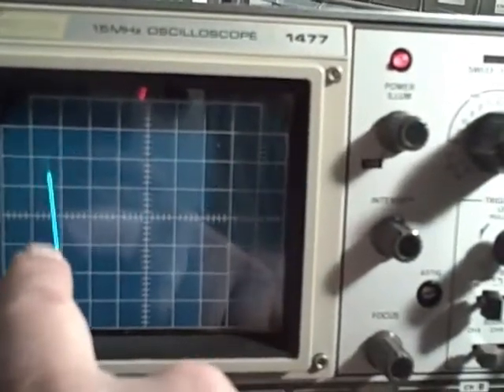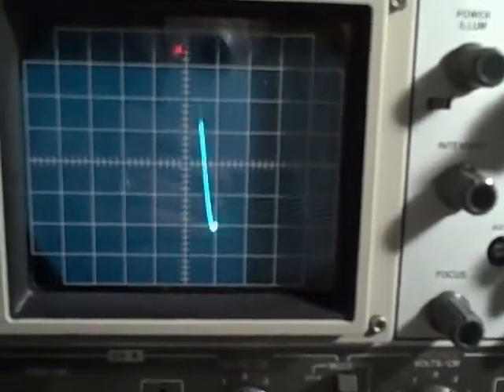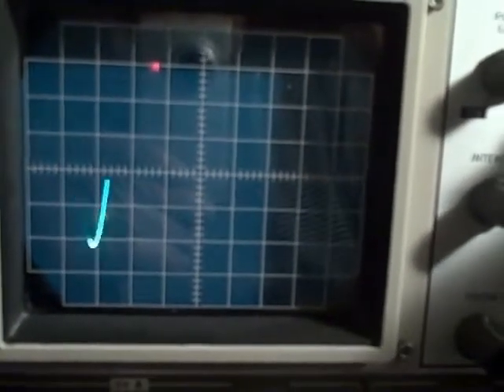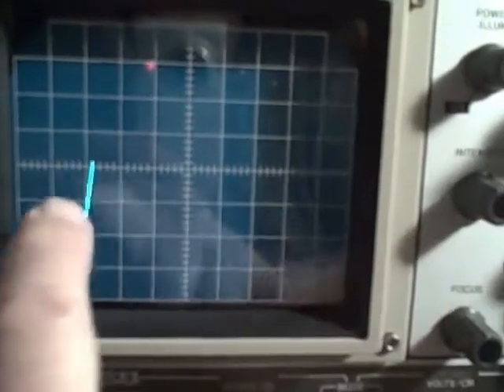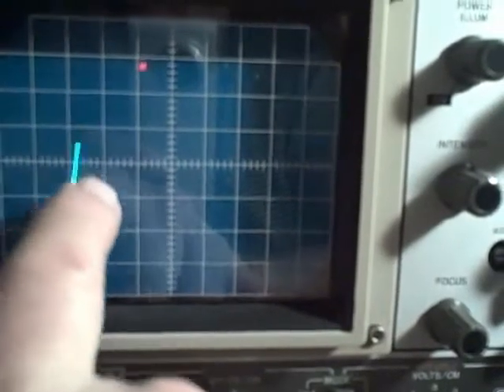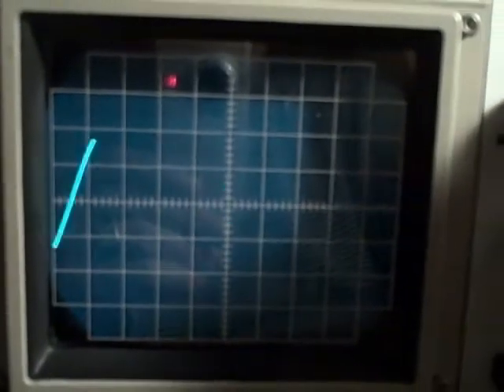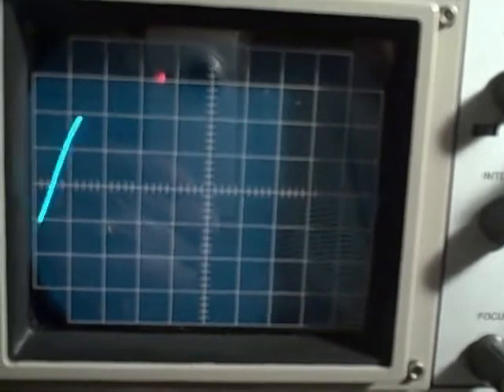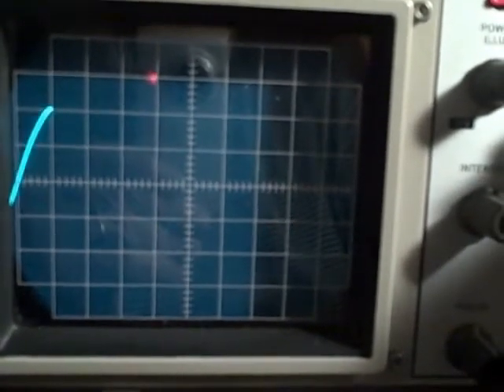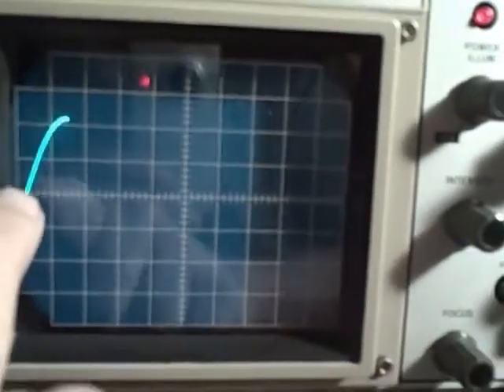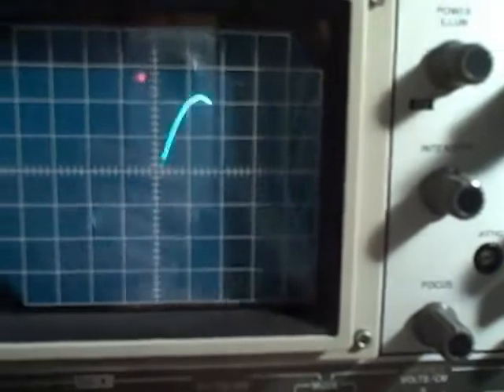At this point we should be seeing one full cycle per division. It's still difficult to see something moving this quickly, so let's expand it. At 50 milliseconds per division it takes two divisions for a cycle — we peak out, come down, peak out, come up again in two divisions, exactly as expected. Going to 20 milliseconds per division, it should take five divisions for a full sweep, and it does.